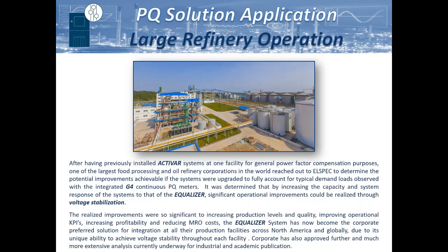The benefit is that if at any time in the future you determine that you need faster response, you can upgrade the controller, and it now has the full response of an Equalizer as well. In this case, the manufacturer called us and said they knew exactly what they wanted, the size and the response rate. We provided that, and they were very happy with the results. They came back a couple of years later when I got involved and we started looking at some of their data. We determined that if we made these a little bit bigger and made them respond quicker, we could create voltage stabilization on the network that would have a much better impact on the facility.